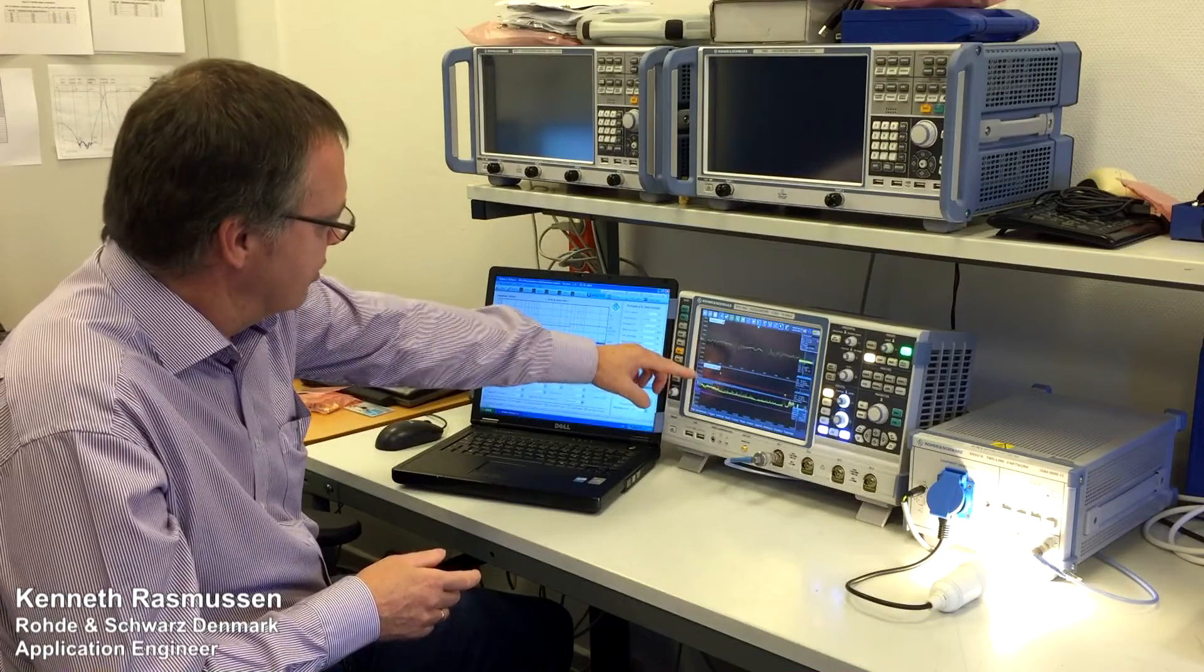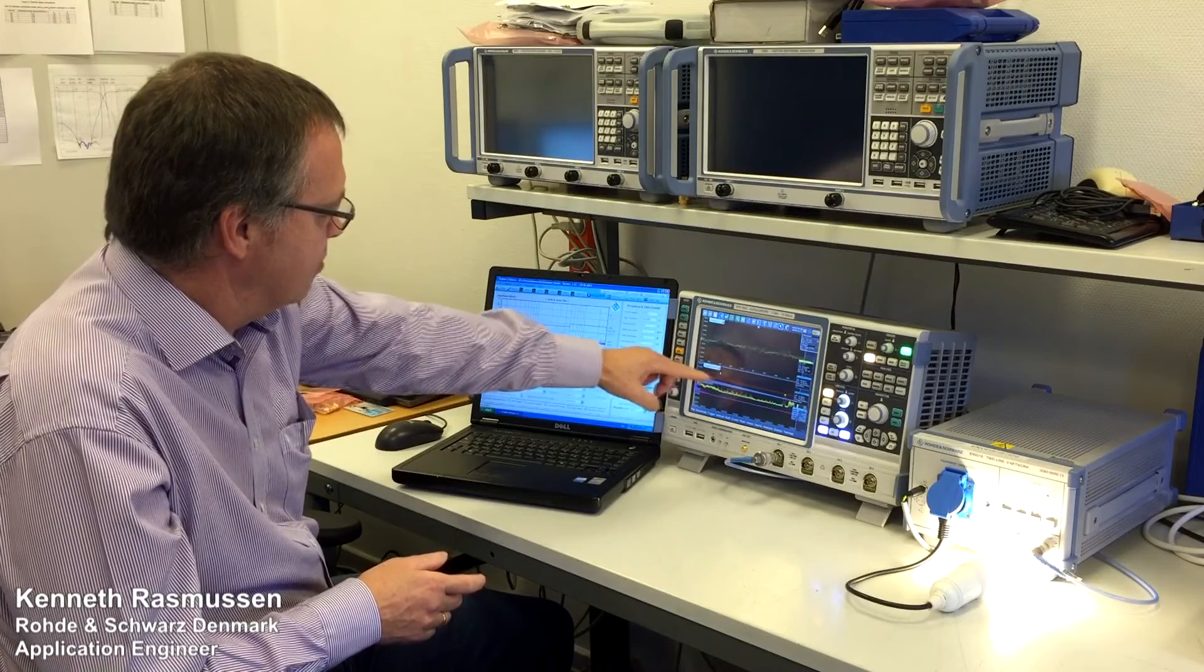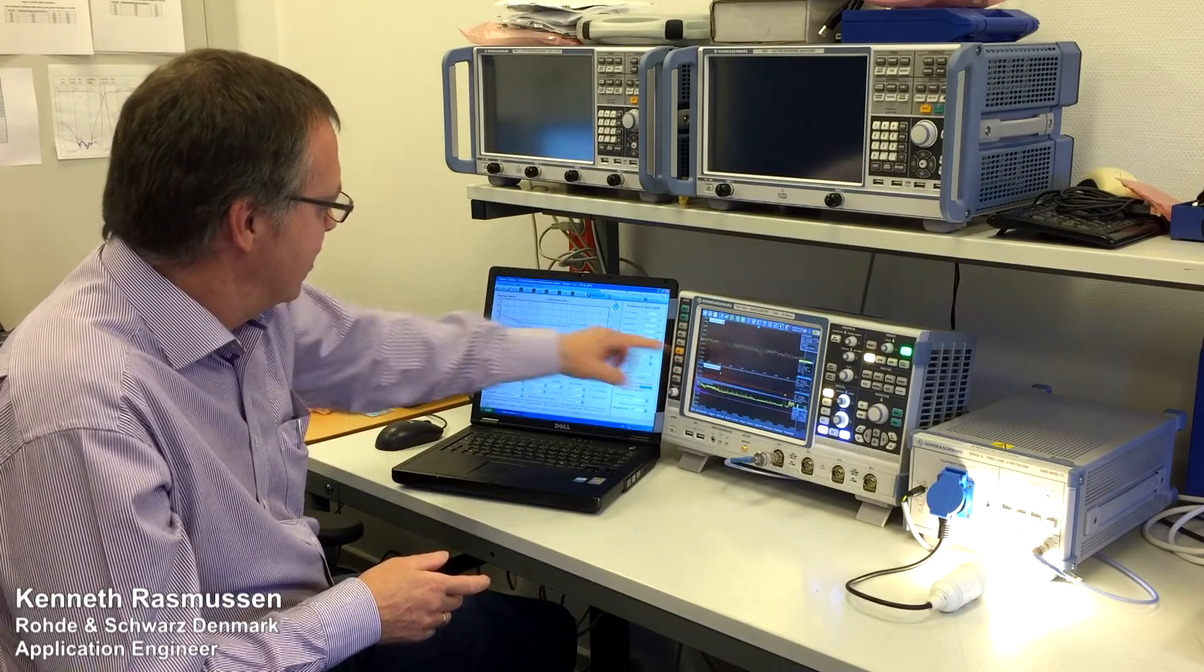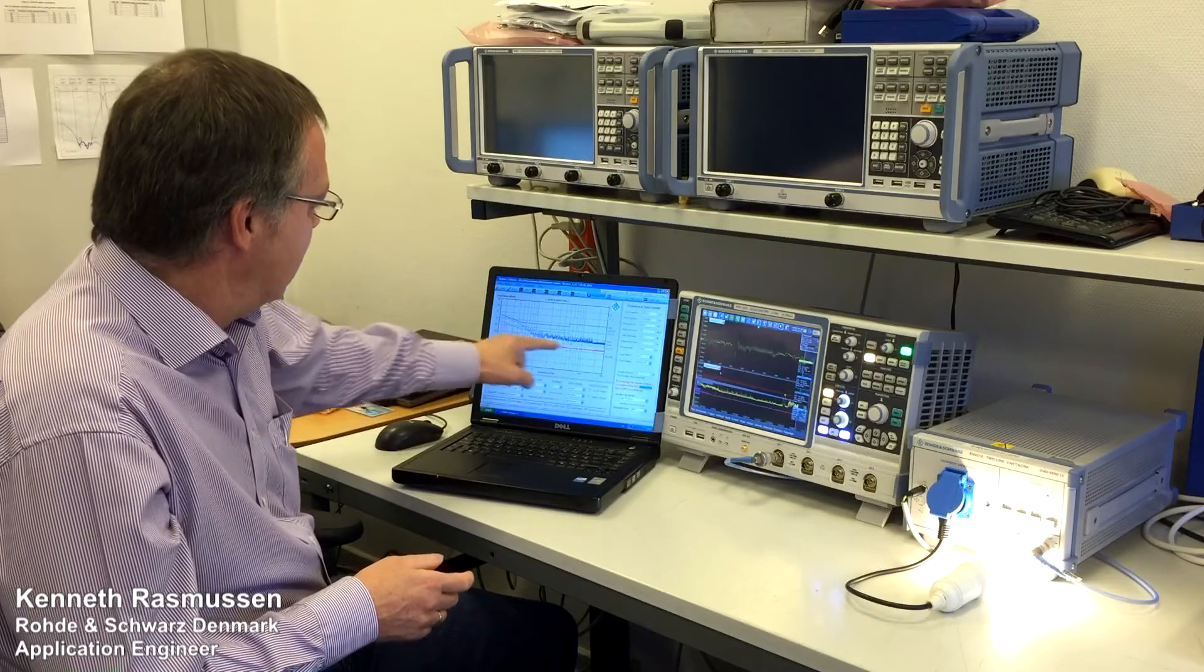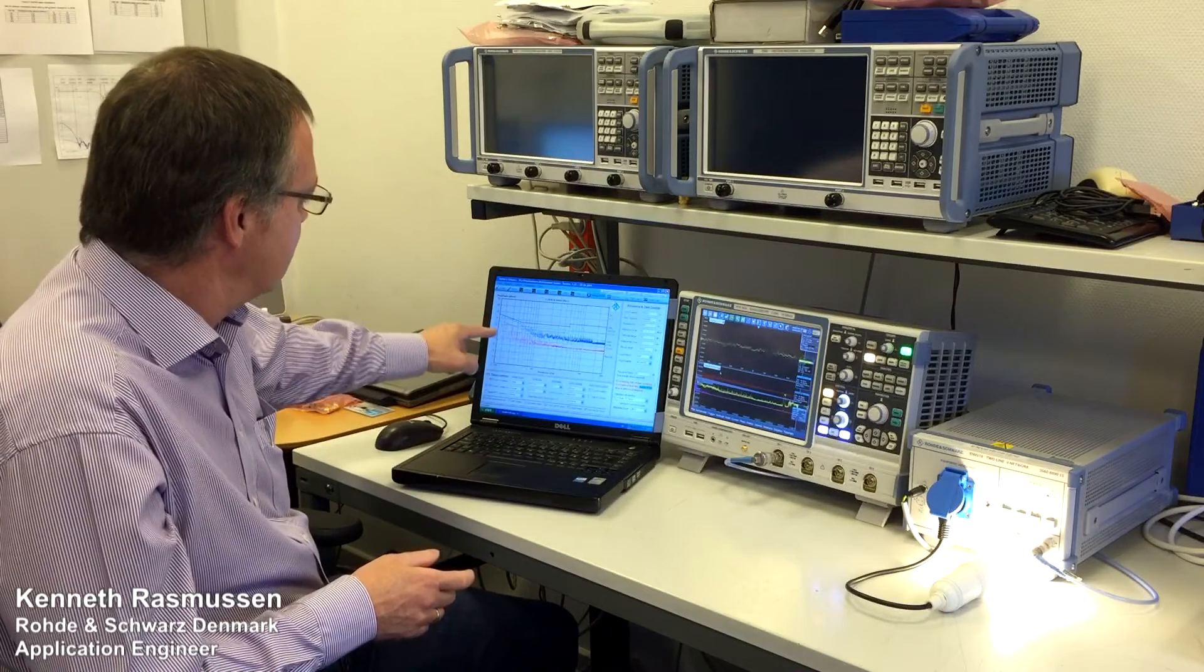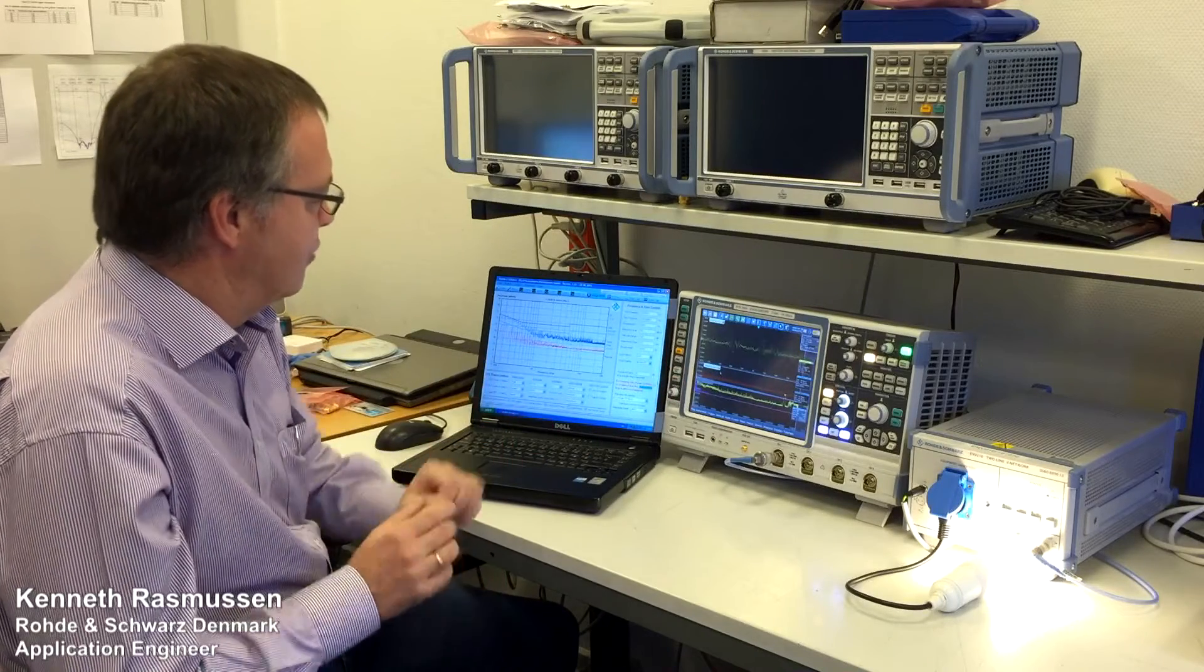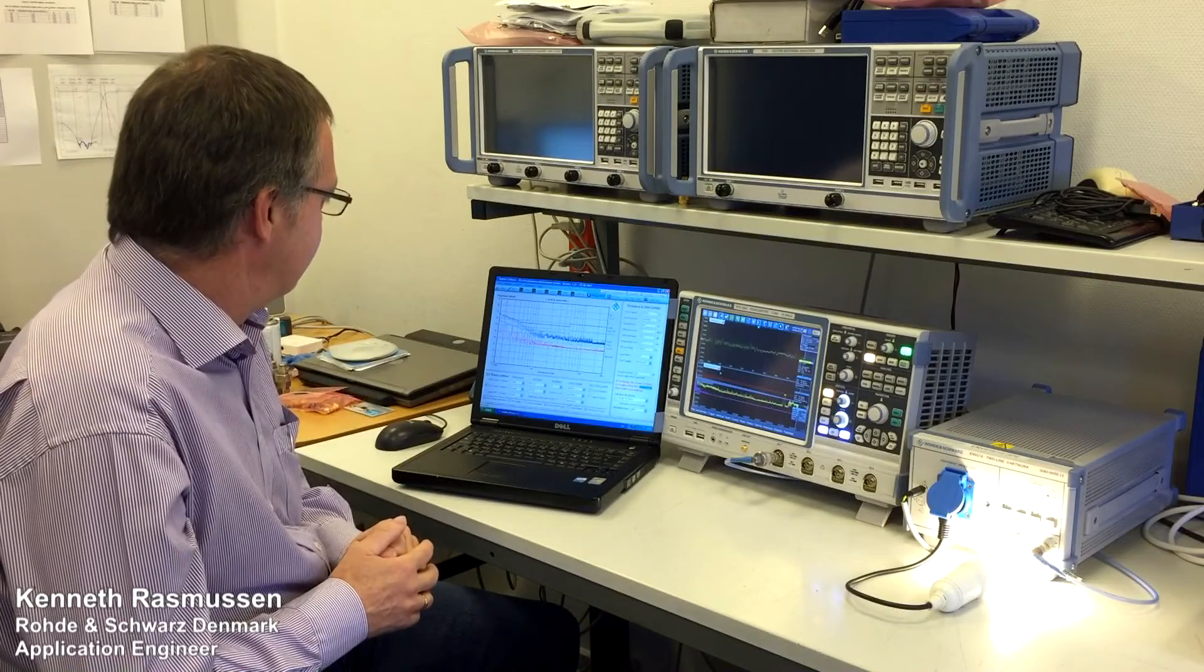We can see that the peak detector here in the lower end is actually violating the limit lines, which is also indicated on the scope here where the top limit line or mask is indicated in red, meaning we have a violation. For the average detector, we are just below or on the limit line, so we have a very close pass here.